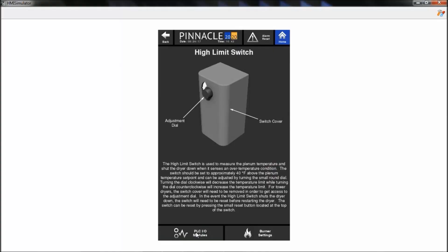We've essentially taken information directly from the manual and brought it into the software, so when you're having trouble with a high limit alarm, you can come directly into here and learn more about what the high limit switch looks like, which might help you find it on the machine. You'll notice buttons at the bottom of these pages to go directly to other helpful pages. If you have a problem with a high limit switch, potentially there's a burner setting that has to change, or potentially you want to go to your PLC I/O modules.